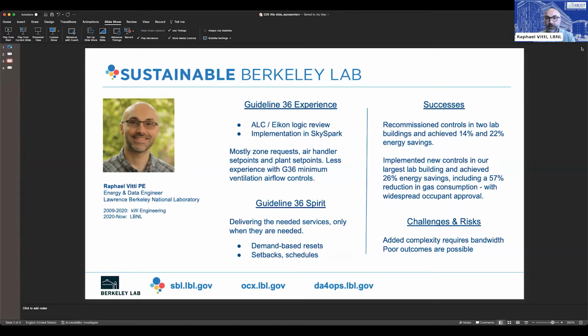We also implemented new controls, and that was a special case where our largest lab building had some reset controls for air handler set points, but they weren't demand-based, they weren't trim and respond, as is the case in Guideline 36. And that building doesn't use ALC, so we decided to actually try and implement the Guideline 36 trim and respond algorithm in SkySpark for the air handler set points.